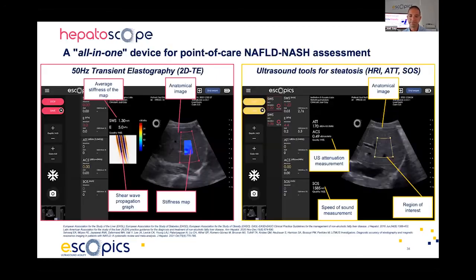So this is how the user interface is presented. I'm not going to spend too much time because we'll have a demo afterwards. You have two modes to use the system. One mode, on the left-hand side, assesses tissue stiffness with a 50 hertz vibration transient elastography, except we do it in 2D, so we're able to reconstruct an image of tissue stiffness. On the right-hand side you have the other modality, which enables retrieving two parameters correlated to steatosis: ultrasound attenuation and speed of sound.